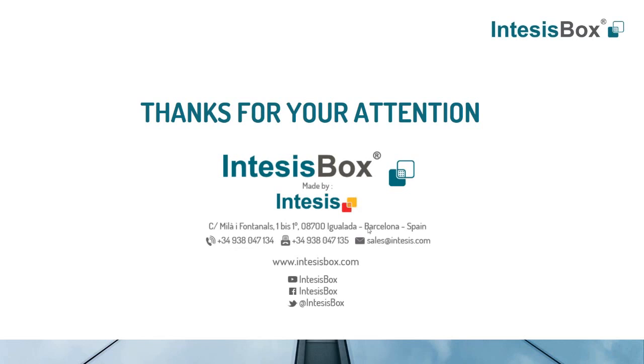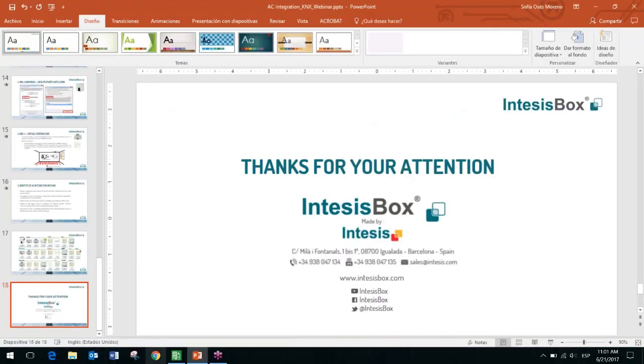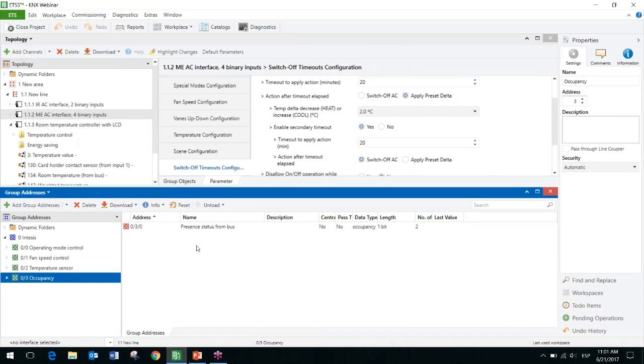Okay, so there is not any separate tool. Are they still seeing my screen, Christian? Yeah, we still see a screen. Okay. There is no separate tool. What we are using is the ETS, the standard software of KNX, and you are just importing the different products that you will use in your project, and then you are getting the data from one device and sending it to the other by using the group address.